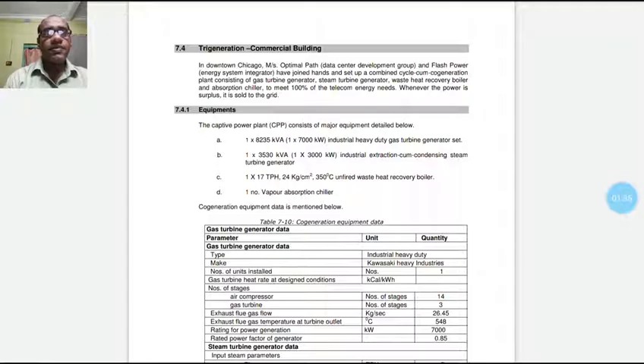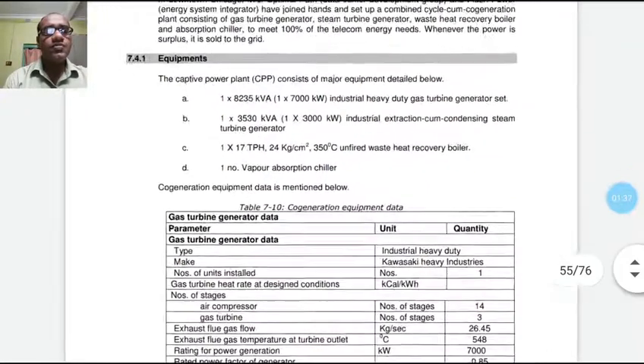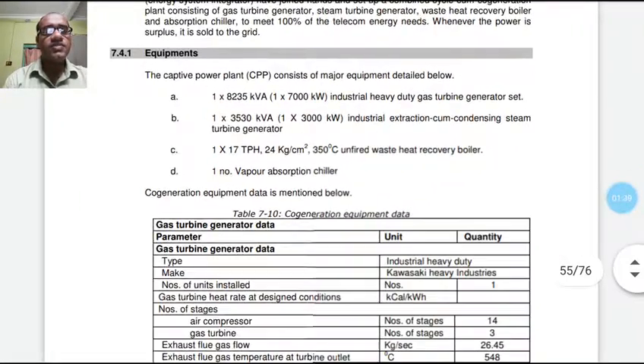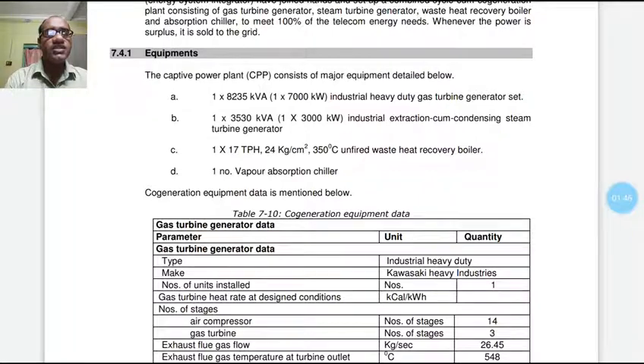The captive power plant consists of the major equipment as given in detail. One number of 8235 kVA, that is 7000 kilowatt, industrial heavy duty gas turbine generator set, one 3000 kilowatt industrial extraction cum condensing steam turbine generator, and one 17 TPH 24 bar 350 unfired waste heat recovery boiler and one vapor absorption chiller.